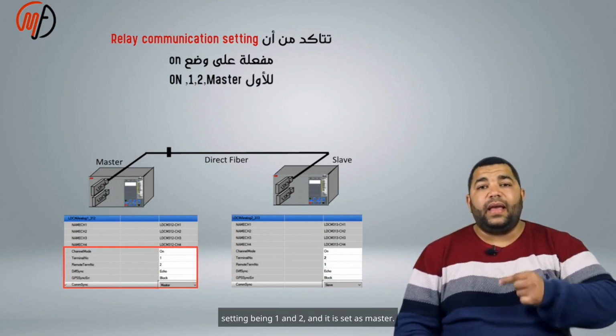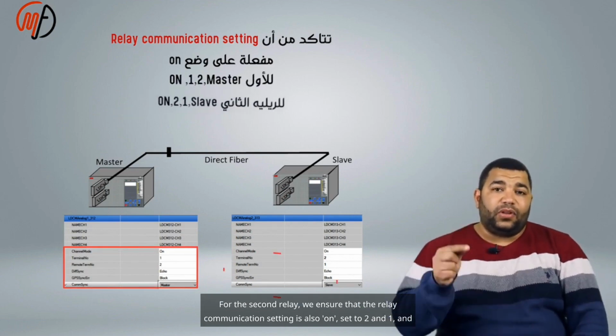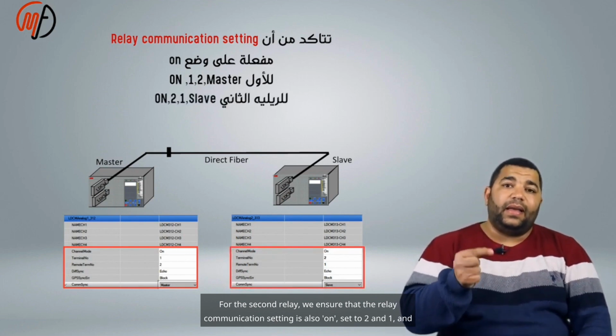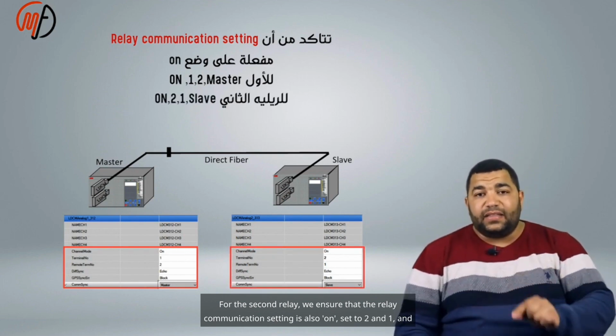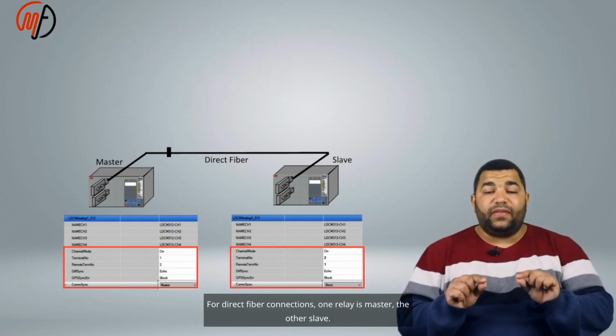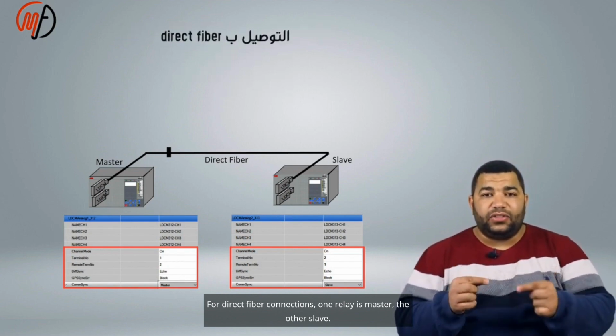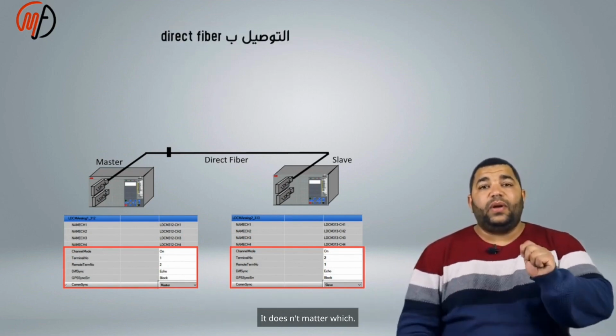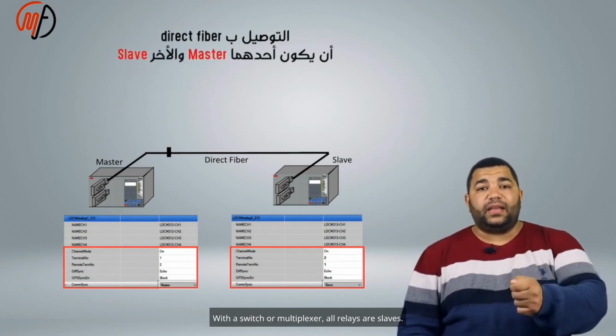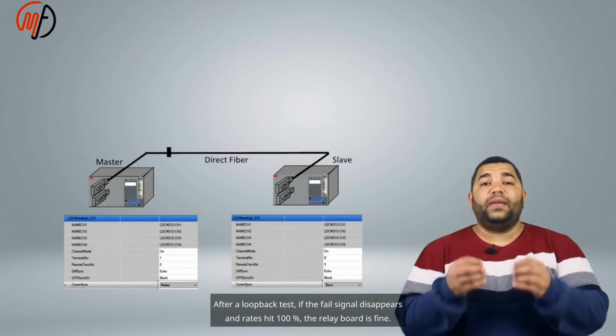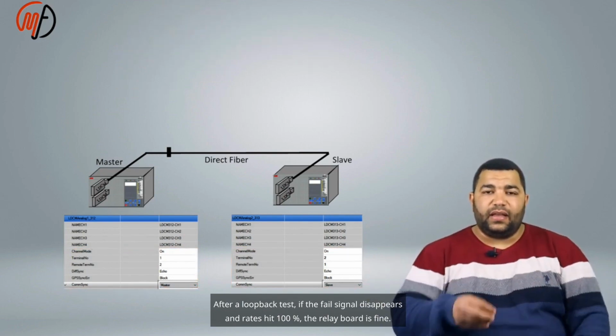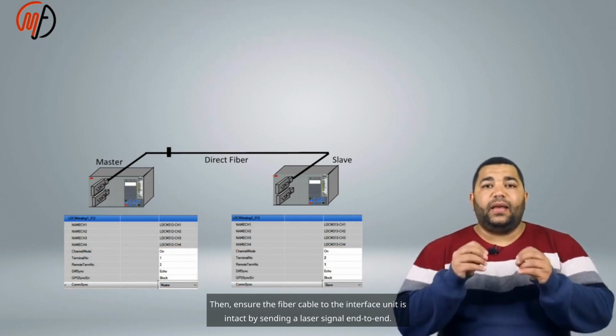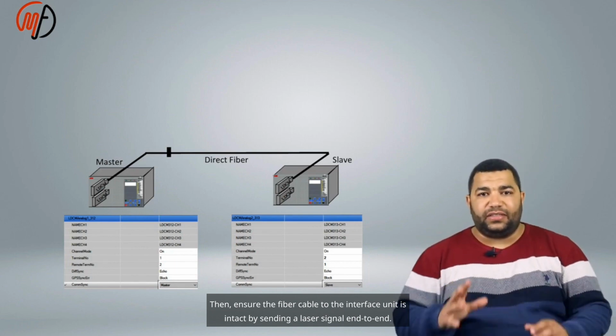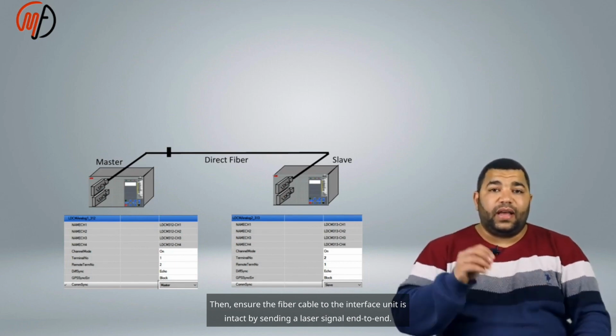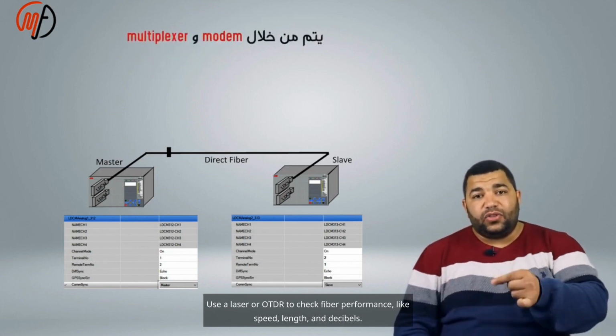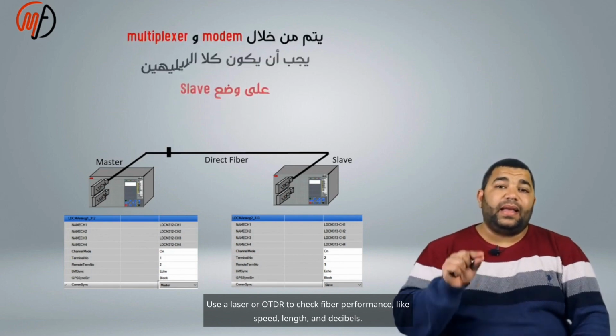For the second relay, we ensure that the relay communication setting is also on, set to 2 and 1, and activated as slave. For direct fiber connections, one relay is master, the other slave. It doesn't matter which. With a switch or multiplexer, all relays are slaves. After a loopback test, if the fail signal disappears and rates hit 100%, the relay board is fine. Then, ensure the fiber cable to the interface unit is intact by sending a laser signal end to end. Use a laser or OTDR to check fiber performance, like speed, length, and decibels.